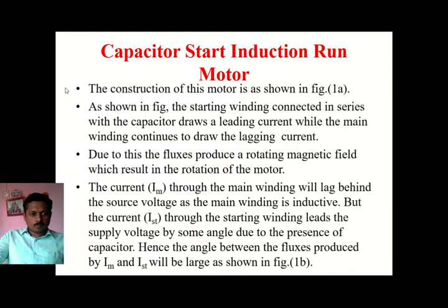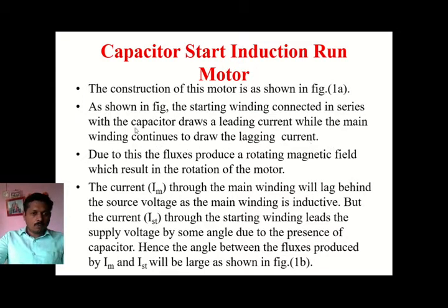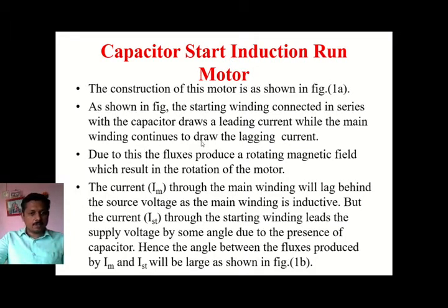As shown in the figure, the starting winding connected in series with the capacitor draws a leading current, while the main winding continues to draw a lagging current. The starting winding draws a leading current because it is the characteristic of a capacitor — when we connect a capacitor, the current leads the voltage. In the main winding we have inductors, and the characteristic of an inductor is a lagging current.